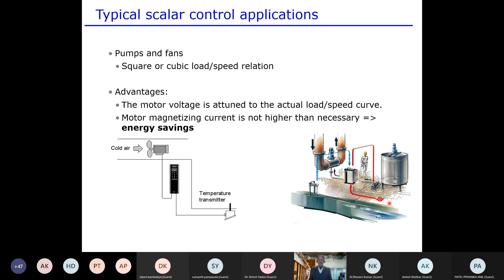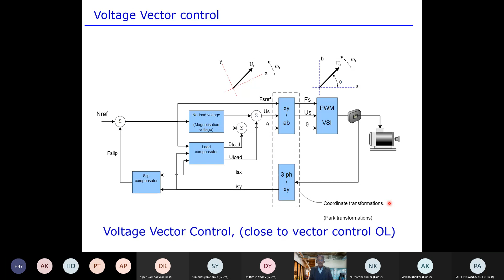This is the voltage vector control. It was a revolution in the drive market, and this is the patented technology of Danfoss. Here we are using the steady state motor model to know the required amount of voltage, as well as the load compensator. So if there is increased demand from the load side, we add extra voltage, and its performance is in between vector control and open loop control.